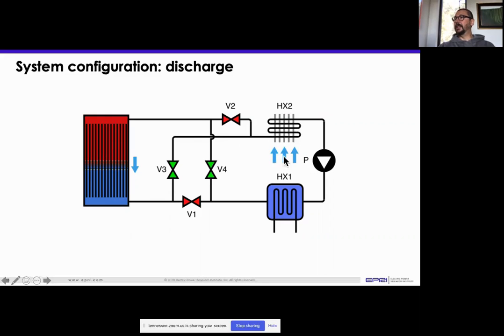This is the heat exchanger that cools down the air going to your house. The warm return air from the house goes through the heat exchanger and cools down, warming up the heat transfer medium, which goes to the pump and through the heat pump heat exchanger. At this moment that's not doing anything, since we're using the cold from the ice storage, so nothing happens to it there, it just goes through, then back through V4, and back down through the heat exchanger.